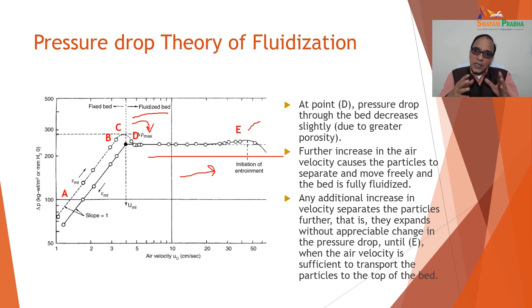Overall, if the air velocity is decreased after that time, the particles fall onto the bottom at the later stage. But this is the actual pressure drop theory of fluidization. We must understand this completely, how pressure drop is controlling it and the rearrangement is occurring, which is offering the least resistance, and then the fluidization occurs. So this is the way we can understand how fluidization is done in the fluidized bed dryer.